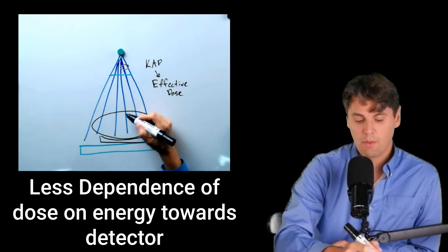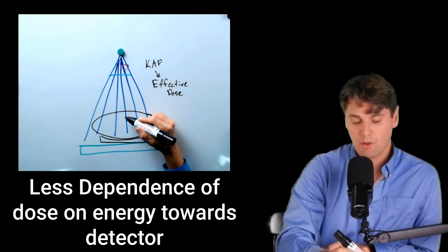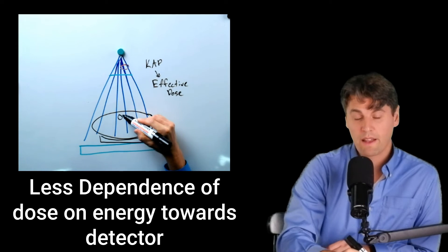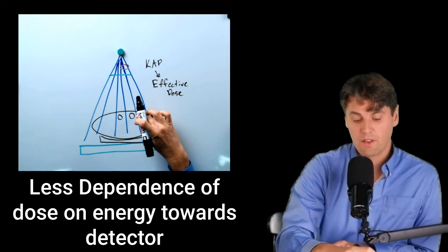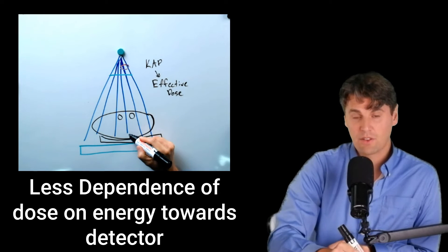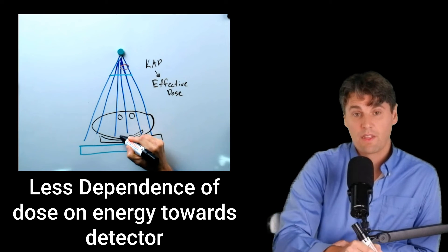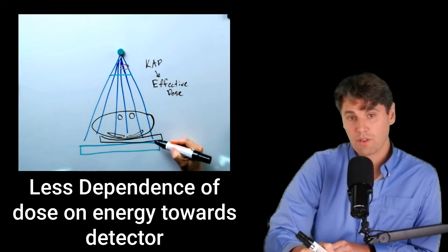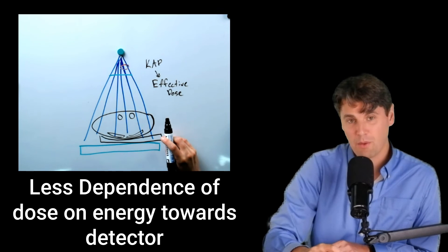When we have our Kerma area product, it's more strongly going to influence the organs which are towards the surface, and it's less strongly going to influence things that are towards the bottom that are closer to the image receptor, assuming that we're keeping the detector signal fixed.